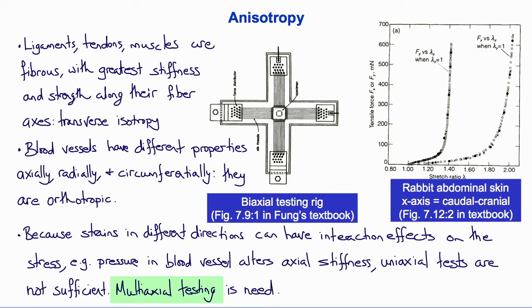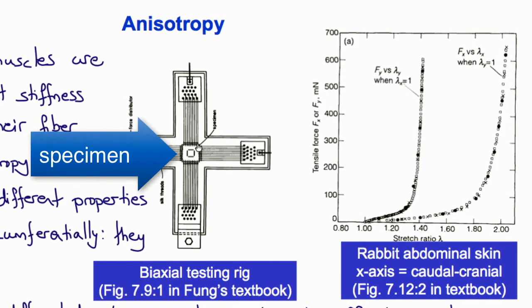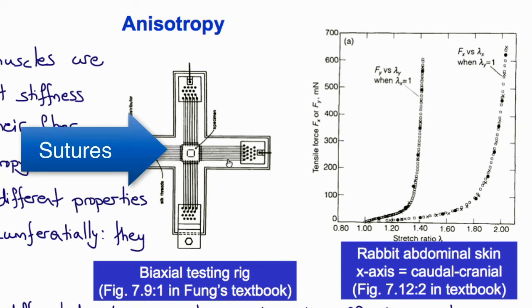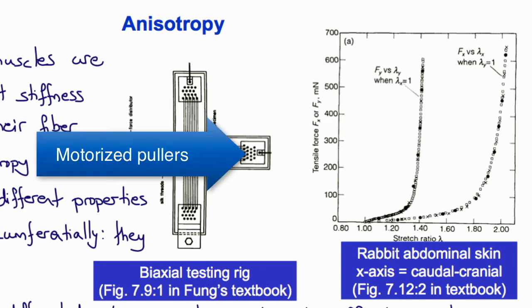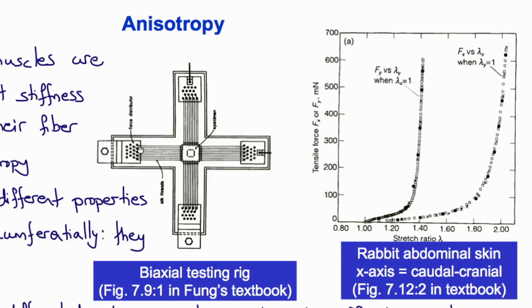A variety of multi-axial test apparatus have been developed, but one of the best known and most versatile is the biaxial test rig. The specimen is attached to long strings connected to pullers. By having these strings be long, as the device stretches the tissue, the angle of the strings doesn't change very much, so the loads remain perpendicular to the edges of the tissue. There are pullers on both sides so the device can pull the tissue symmetrically and leave the center of the specimen centered.